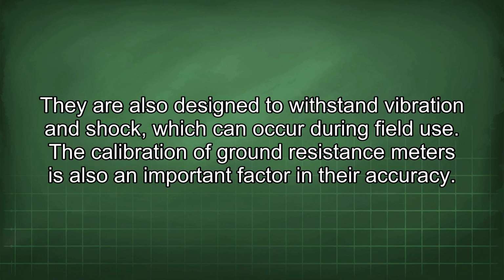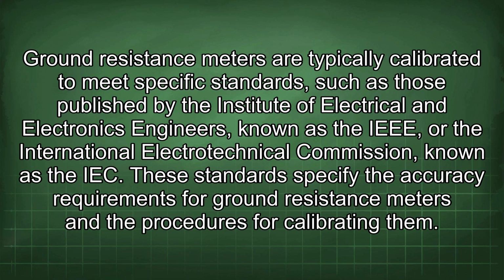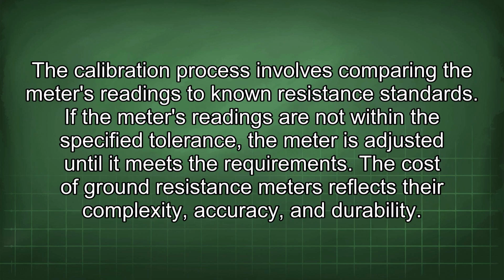The calibration of ground resistance meters is also an important factor in their accuracy. Ground resistance meters are typically calibrated to meet specific standards, such as those published by the Institute of Electrical and Electronics Engineers, known as the IEEE, or the International Electrotechnical Commission, known as the IEC. These standards specify the accuracy requirements for ground resistance meters and the procedures for calibrating them. The calibration process involves comparing the meter's readings to known resistance standards. If the meter's readings are not within the specified tolerance, the meter is adjusted until it meets the requirements.